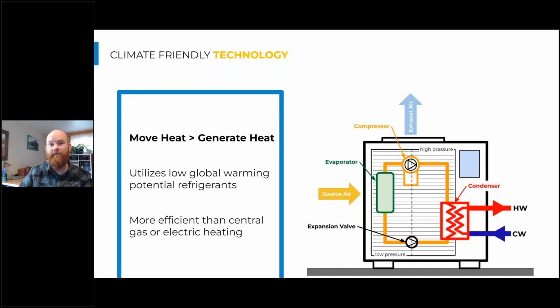Compare that to a heat pump water heating system, and you have a much smaller amount of refrigerant all packaged together. And that packaging took place at the factory, a much cleaner, much more stable environment for us to work in. Whereas in the building environment, some of that refrigeration piping might have been installed under poor weather conditions or under a strict timeline because the crane was only serving for some aspects of the day. So there's more room for error in those larger systems that are using those refrigerants that are fairly toxic. So heat pump water heaters are really advantageous in that regard because they are moving towards less toxic refrigerants with lower global warming potential, but are also, the refrigerant that they have in them is a fairly small volume compared to those larger systems. So there's a great advantage there.